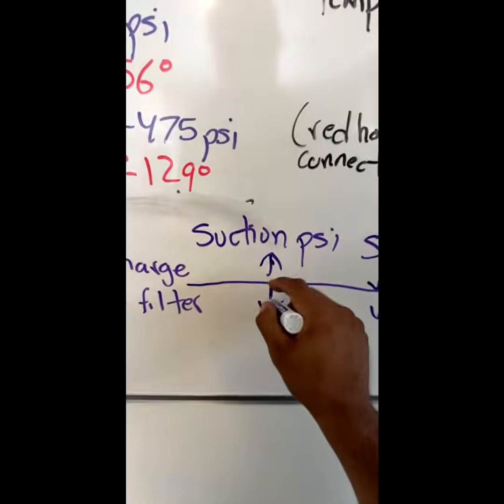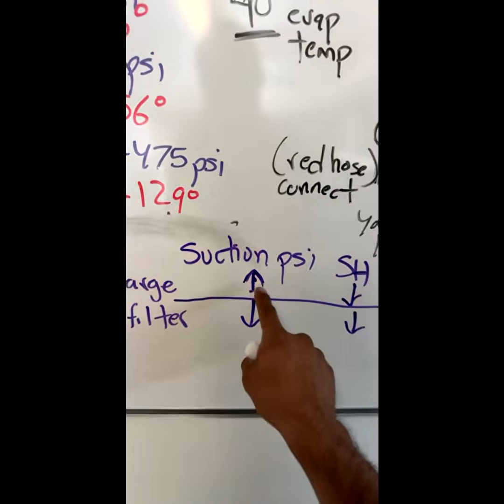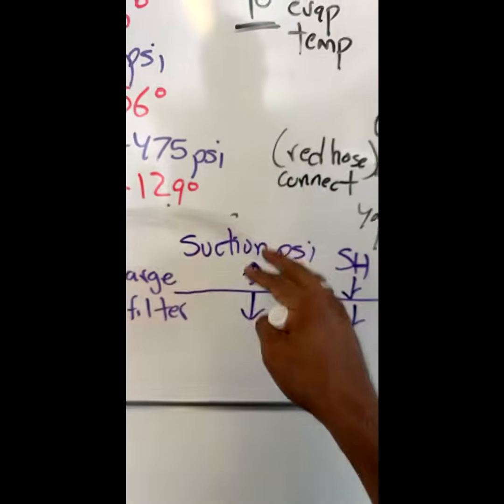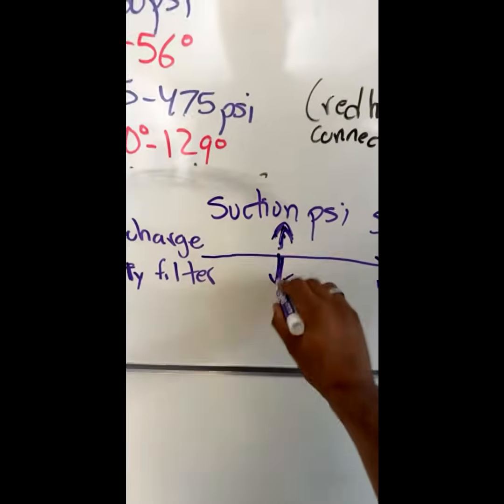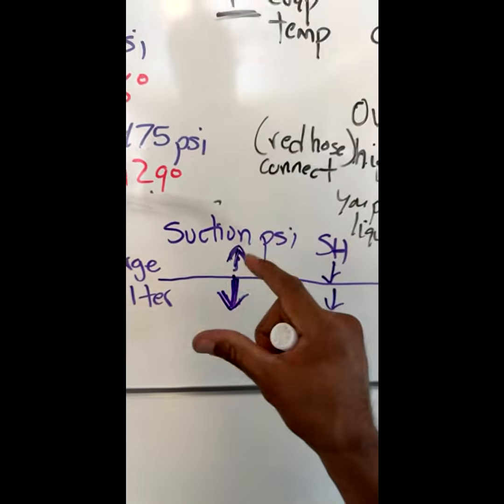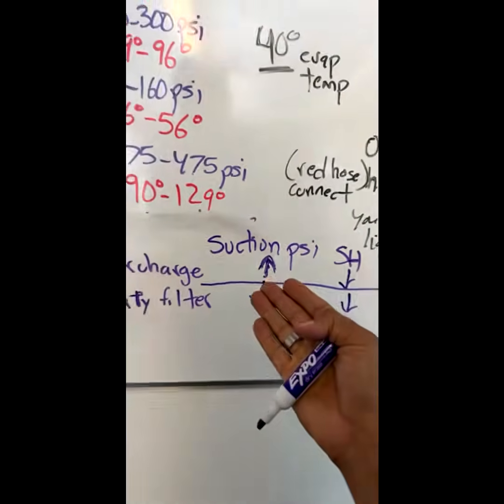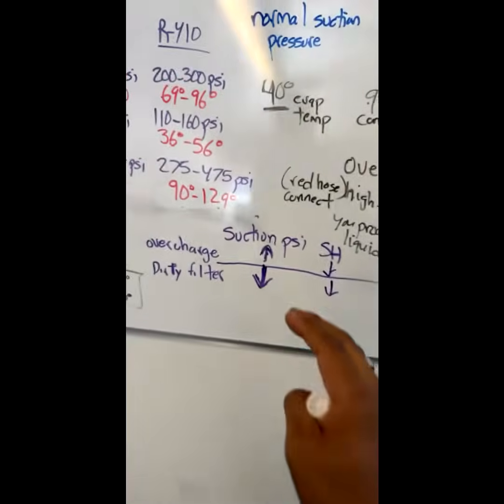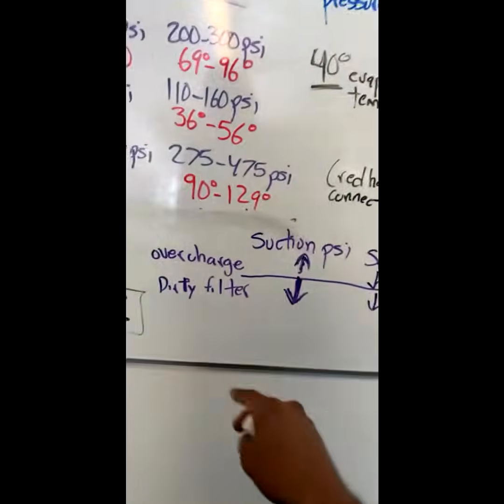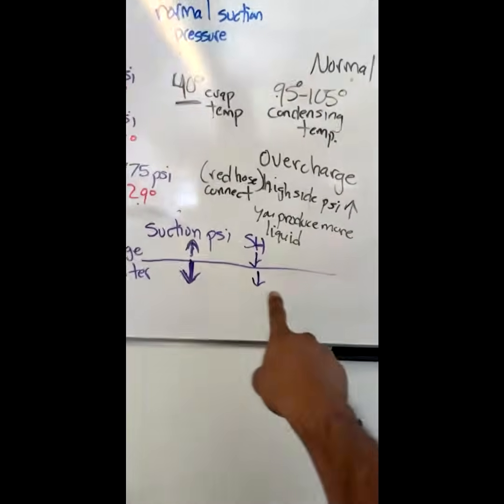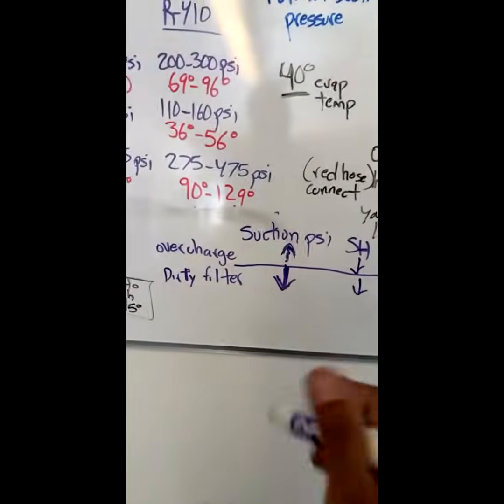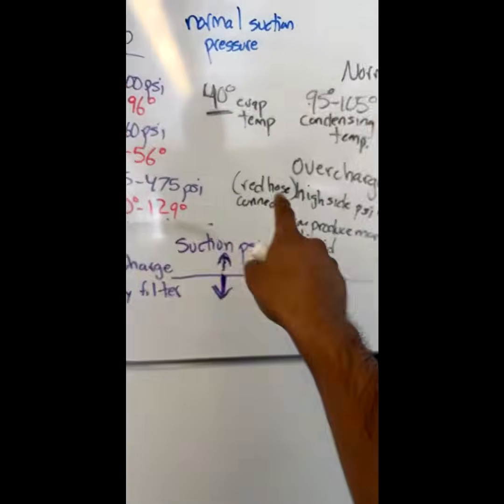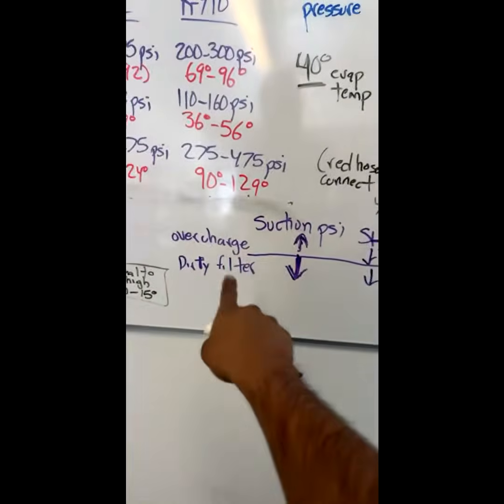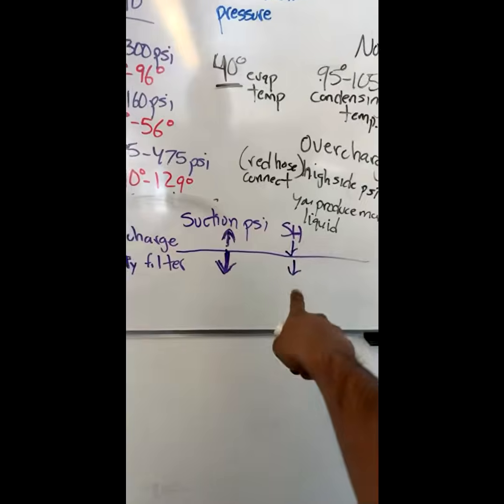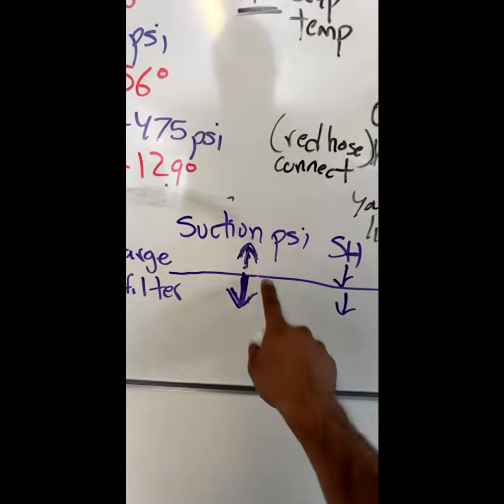Overcharged system, your suction pressure is going to be higher, even if it's a TXV and it modulates. But if it's really overcharged, your suction pressure is going to be high. With a dirty filter, though, it's going to be low because the TXV is pinching down. It's like, hey, that suction line temperature is kind of cold, let me pinch down, allowing less liquid refrigerant to go to the evaporator. So that's the difference between these right here, right? Overcharge: high suction pressure, low superheat. Dirty filter or low airflow: you see, my superheat is still low, but my suction pressure, this is a dead giveaway right here.